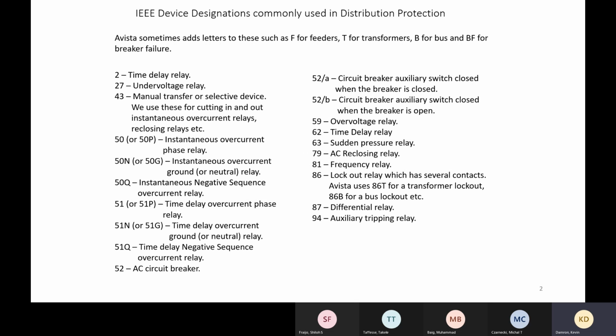So hopefully most of you are familiar, and I know at least from the previous week that you'll recognize a couple of these numbers. These are some of the most common numbers that you're going to run across, and they're IEEE, Institute of Electrical and Electronics Engineers, device designations. The nice thing about this is it keeps all protection engineers and substation engineers, everybody looking at substation drawings, on the same page. If I look at a 50, I know that's an instantaneous overcurrent. If I look at a 51, I know that's a time delayed overcurrent. 52 is a breaker. Breakers have A and B contacts. 79 is a recloser. 81, there was some discussion of frequency elements. Those are 81s. I know Michael had brought up a differential relay, that's an 87. So a lot of these are pretty common numbers.